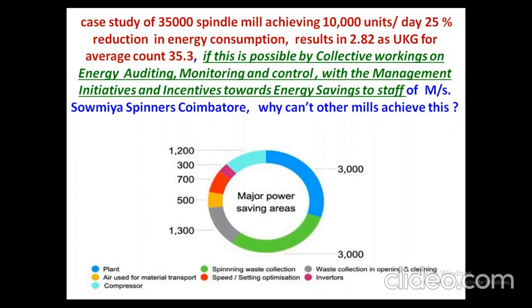At the same time, the health of the machines is improved, as well as the productivity of the machines, and with optimum energy consumption. I don't say minimum, I'll say it's an optimum energy consumption. I'll just go in depth into the specifics of the energy savings done in this mill.